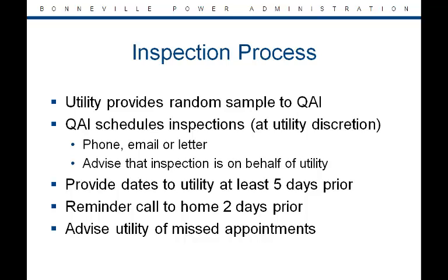The inspector may, at the utility's discretion, schedule appointments for inspections, advising homeowners that the inspections are on behalf of the utility. The utility should not have less than 5 days advance notice of inspections so that they may attend if desired, and the homeowner should get a reminder call 2 days in advance. Advise the utility of any missed appointments so that they can provide alternative sites for inspection if available.